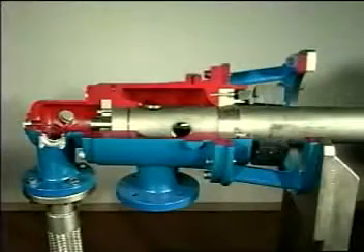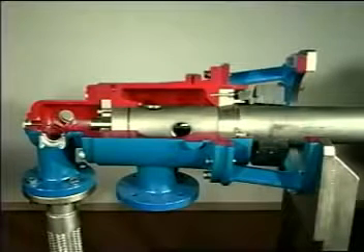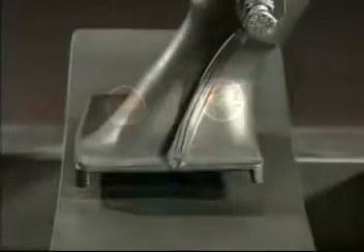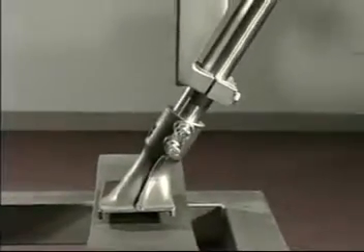Rigidly supported by the machine's frame, the system requires no internal support or bushing inside the dryer to support the siphon. The two widely spaced supports reduce vibration and deflection of the horizontal pipe, enabling the siphon pickup shoe to be mounted at a close clearance to the dryer surface, 160 thousandths of an inch. This reduces the thickness of the condensate layer and increases the heat transfer to the surface of the dryer, making the dryer more efficient.